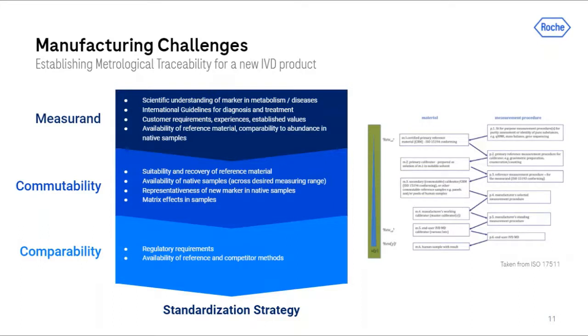In a second step, one needs to look into the commutability of potential reference materials: what is their composition, and what is the recovery of native samples when calibrating the IVD product with the reference material? Is there any matrix effect? Is the reference material representative for the measurand in native samples? Finally, the third step focuses on comparability: are reference methods available and accessible? If not, are there serum panels with assigned target values available for a validation study? What are the regulatory requirements for comparability to a reference or predicate device?